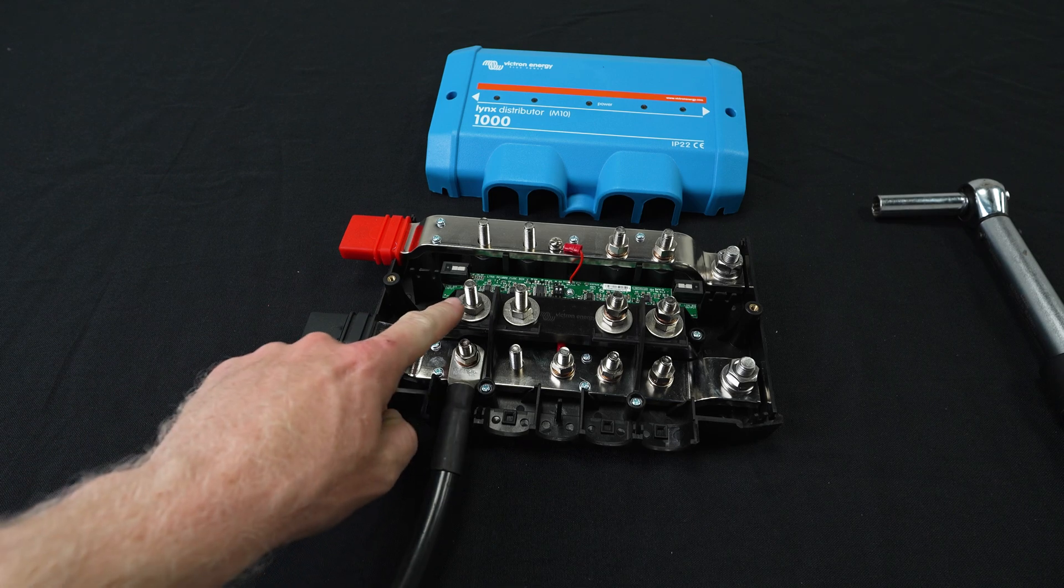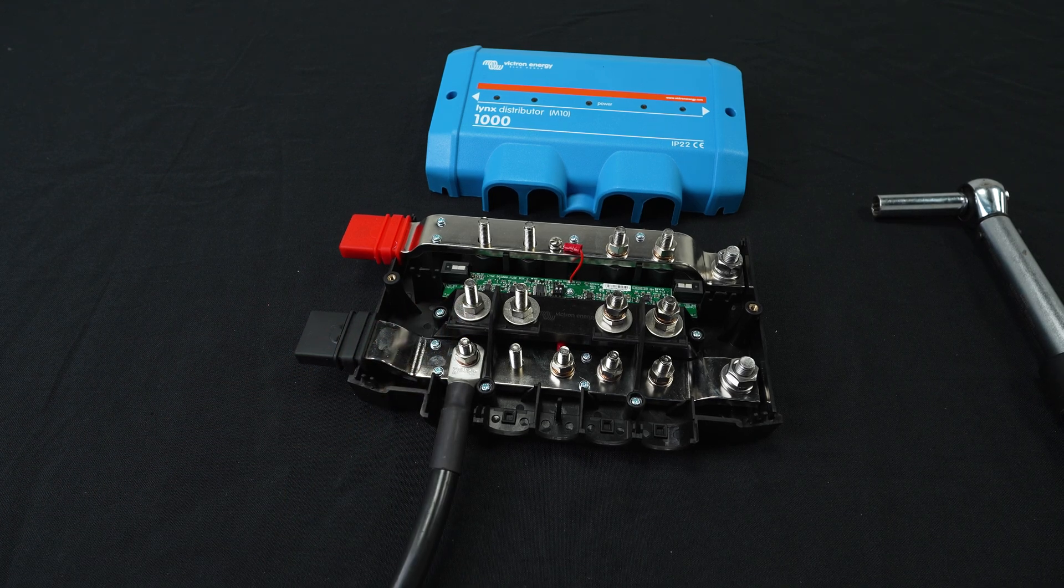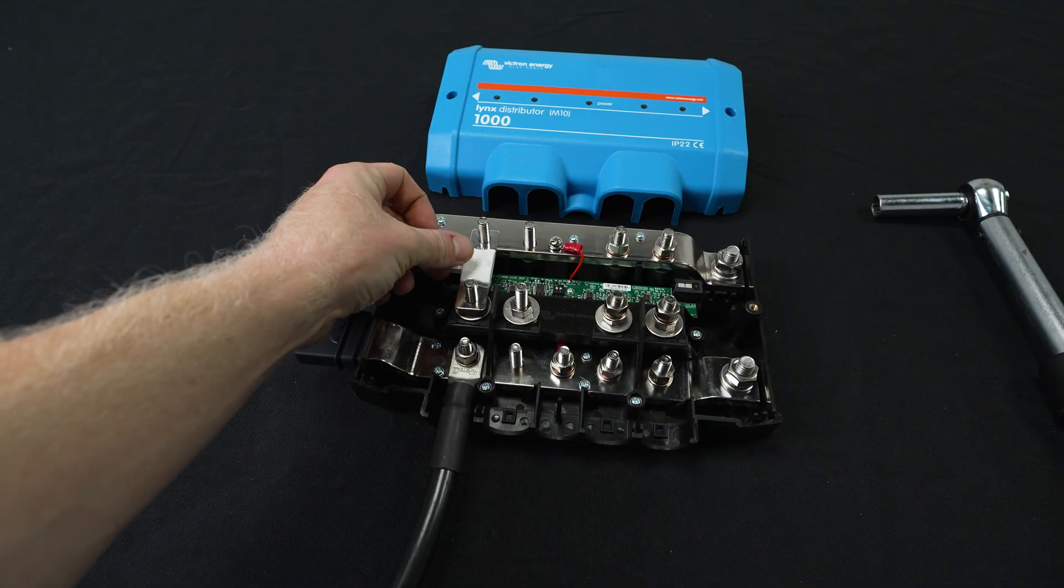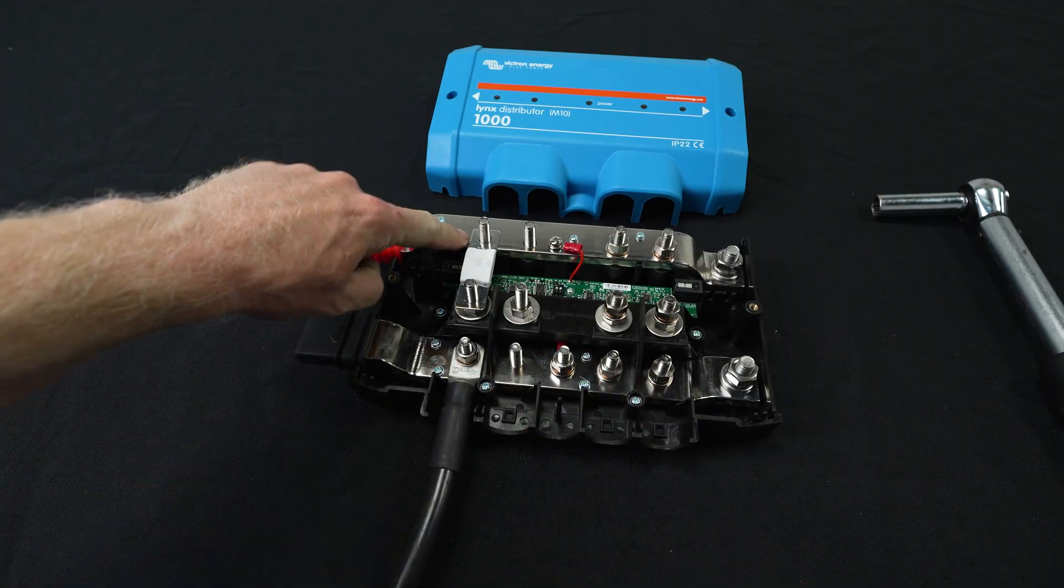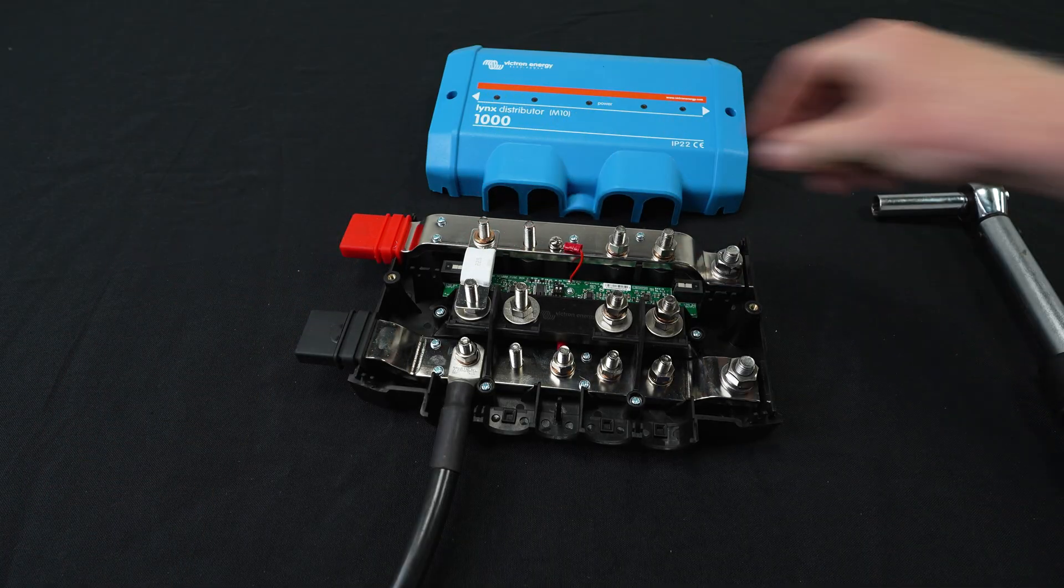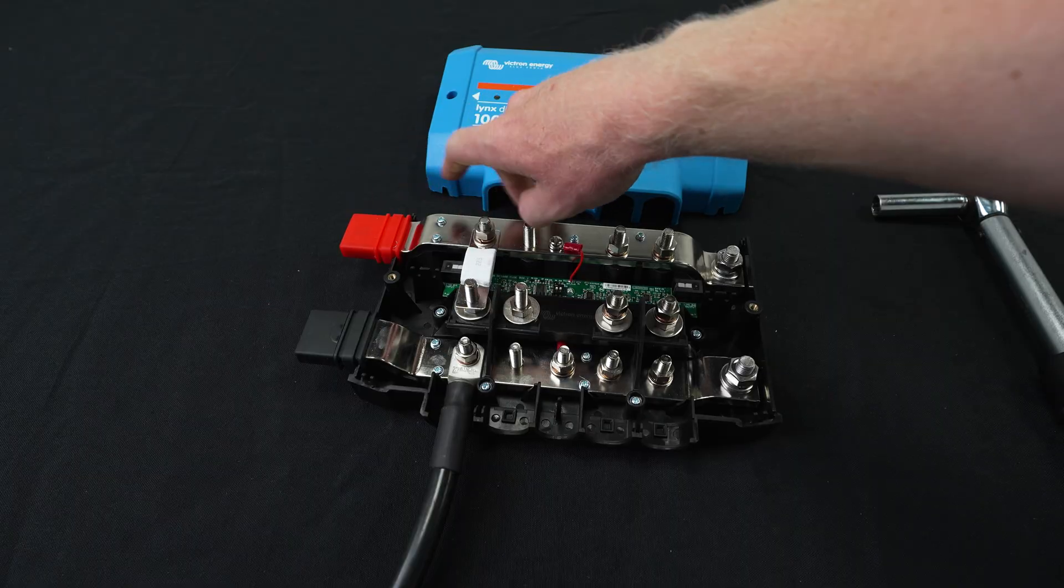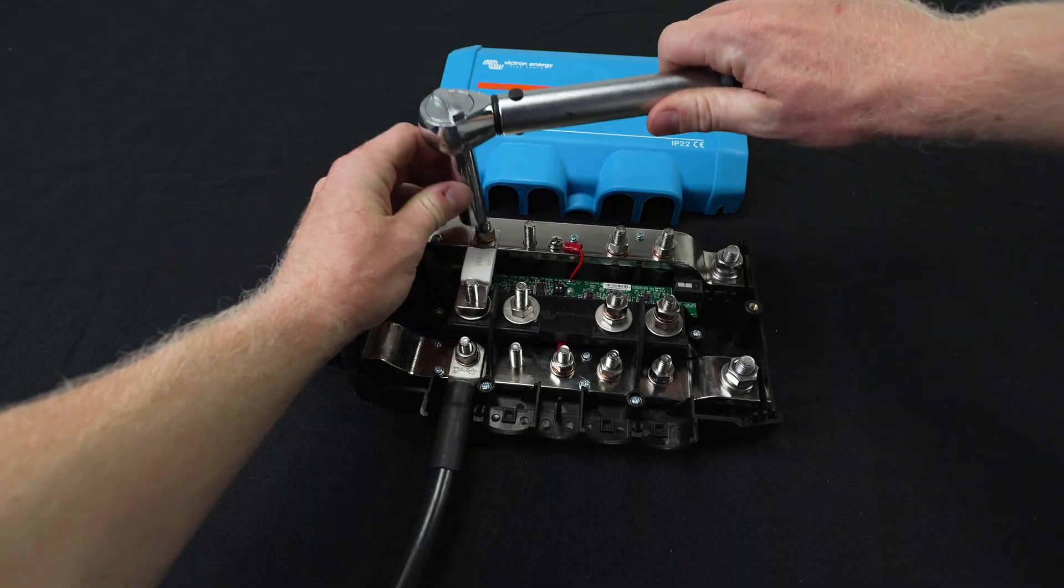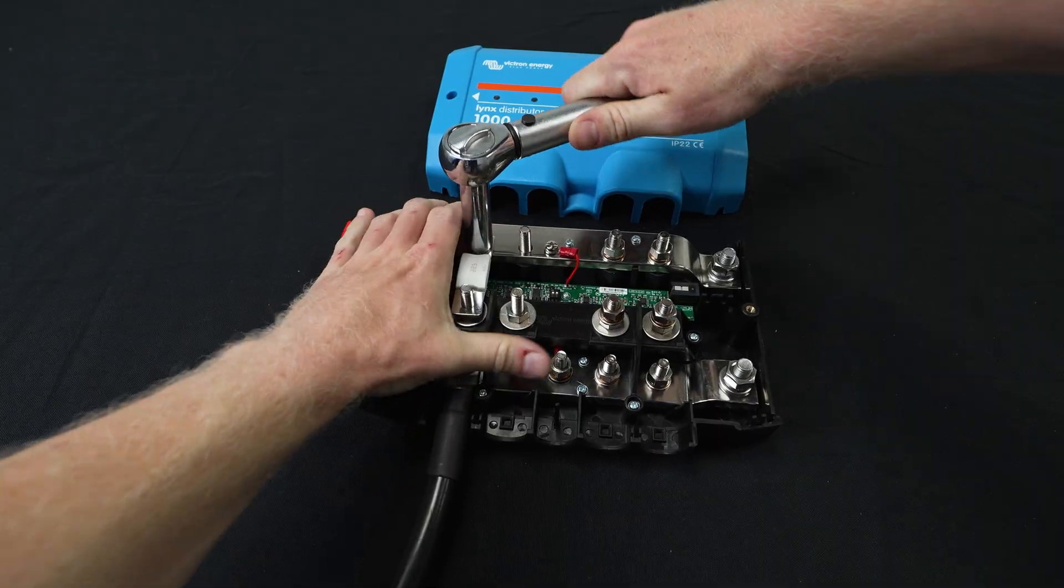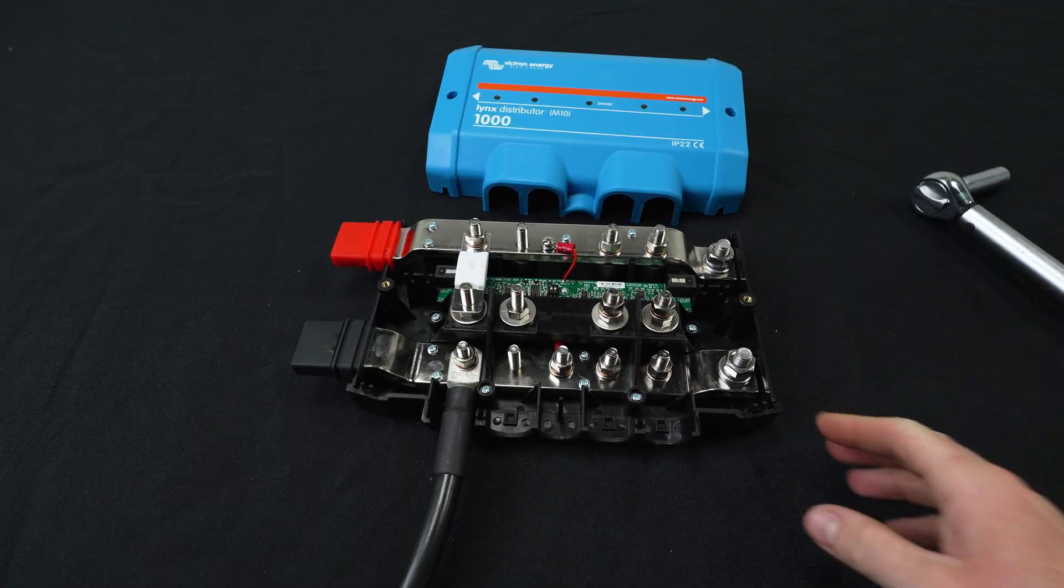Now we can land our fuse here first. So for this 2 AWG cable, I'm going to be using a 225 amp fuse. Again landing the fuse directly on the bus bar, then the flat washer, the lock washer, and finally the nut. We're again at 14 newton meters. And we're tight.